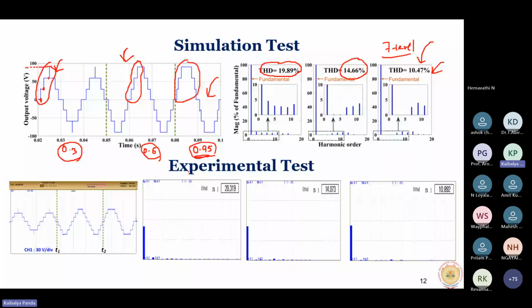This is also verified experimentally at three different modulation indices, changed dynamically. Through the programming, we changed the modulation index from 0.3 to 0.6 to 0.9. This way, you can target low order harmonics, and these can be eliminated from the output voltage of a multi-level inverter. I hope this is clear.